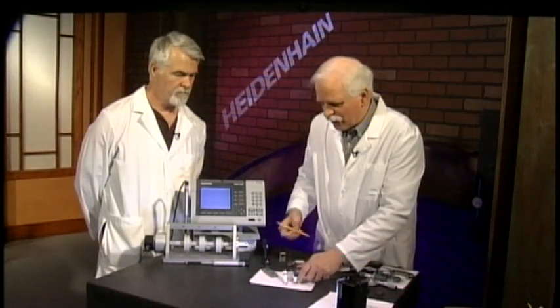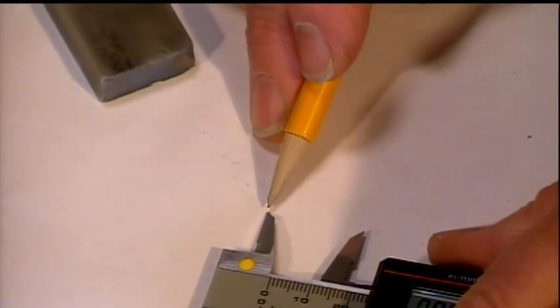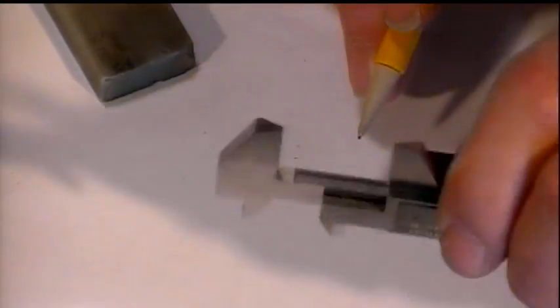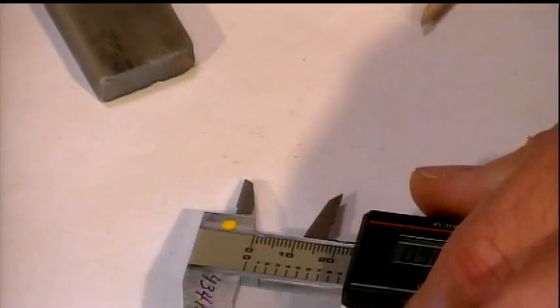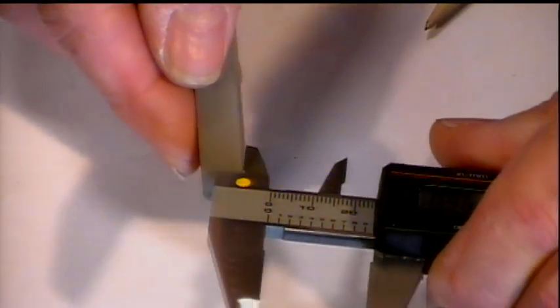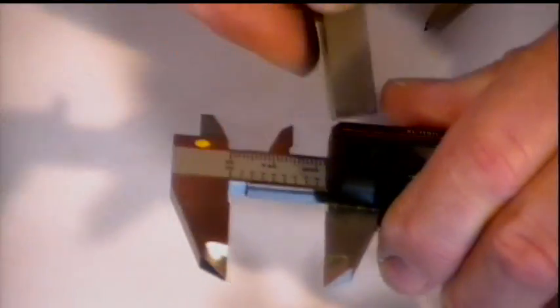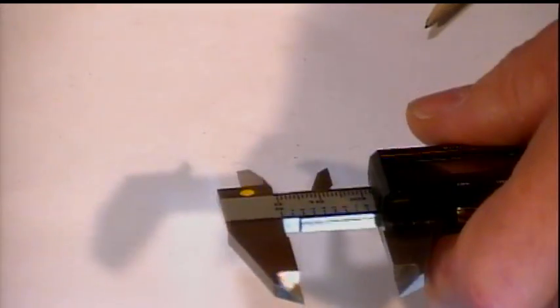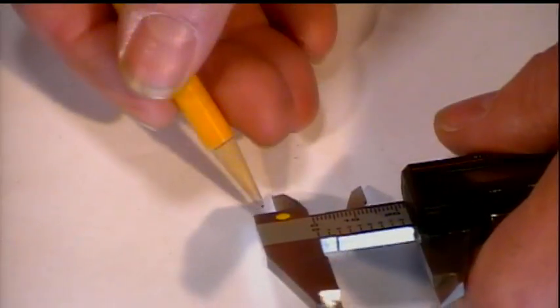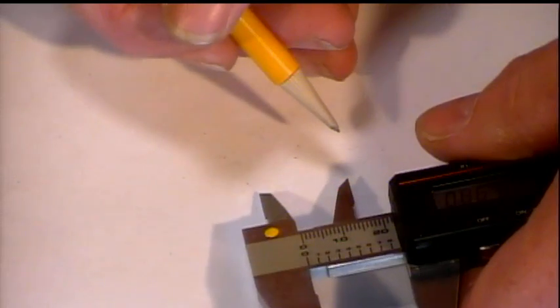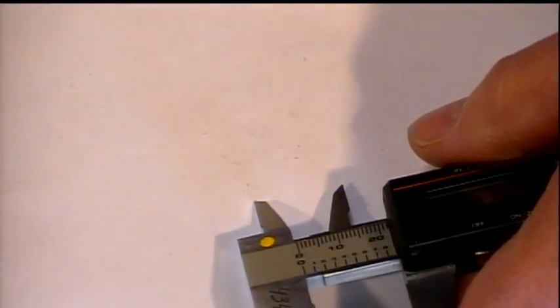A lot of the ID jaws get damaged. We'll find a lot of damage on these ID jaws. They get dropped, they get smacked, they get worn. Again, with the stone, if you have to, one swipe out. Now these aren't knife edge. A lot of people think these are knife edge. These are actually surfaced. They have some width to them. And that would be something I'll cover on the use of them.